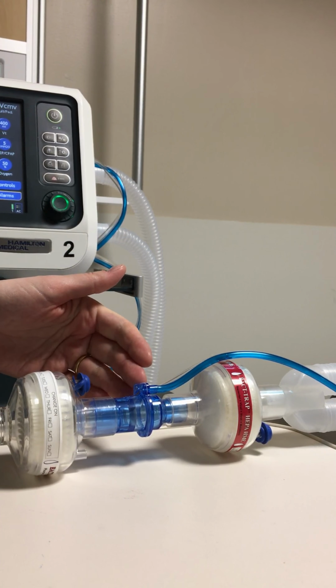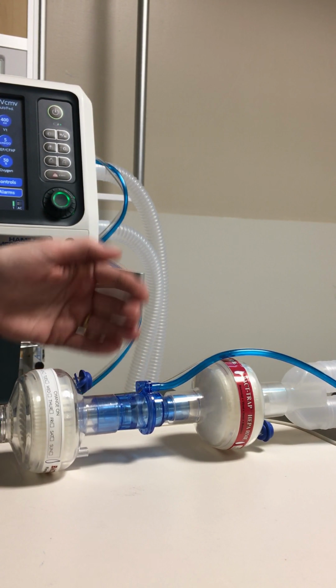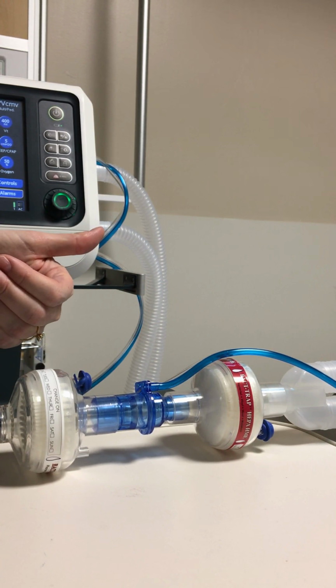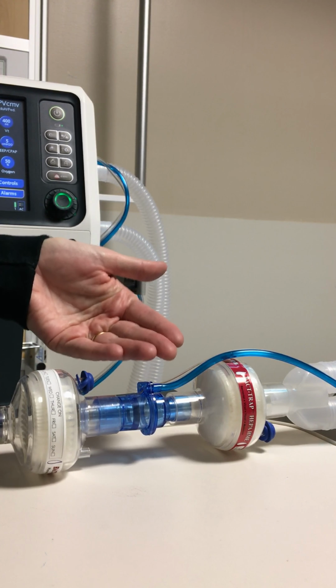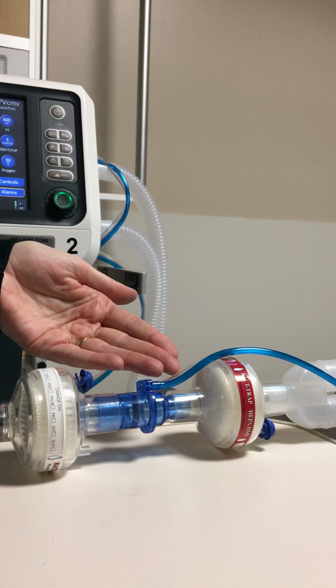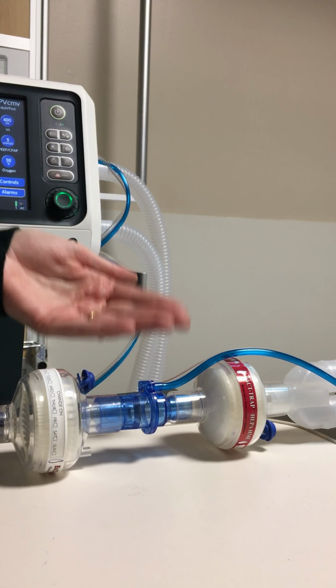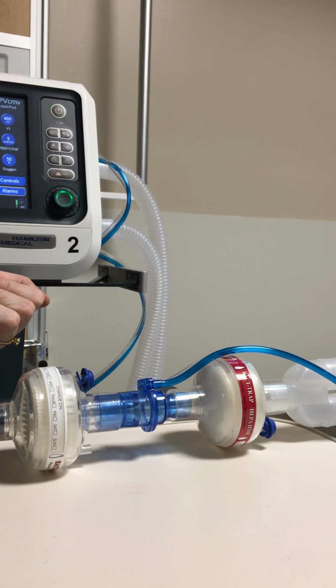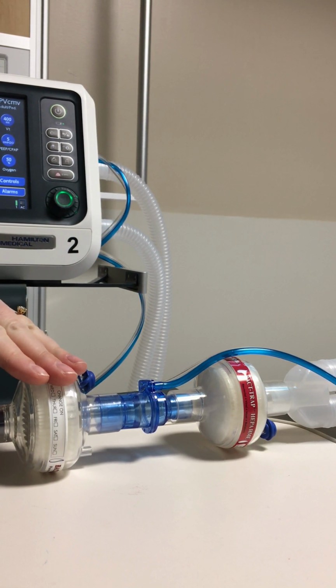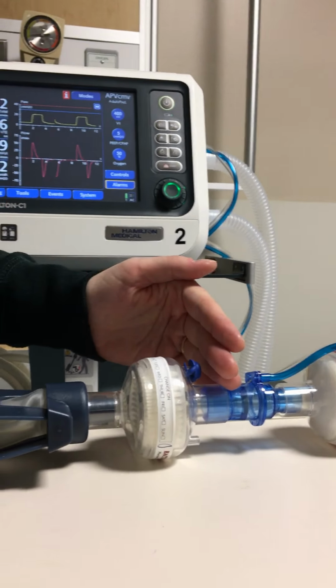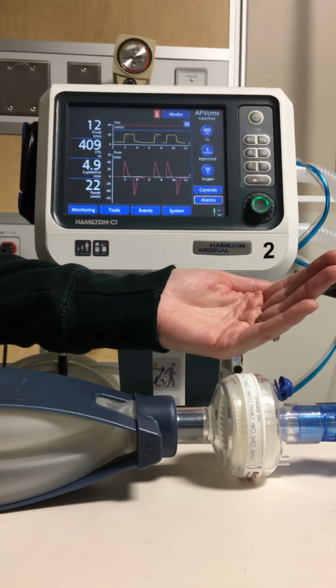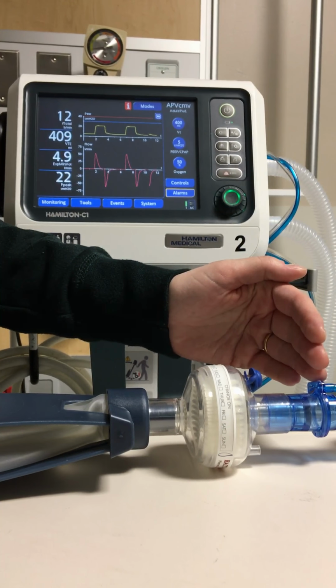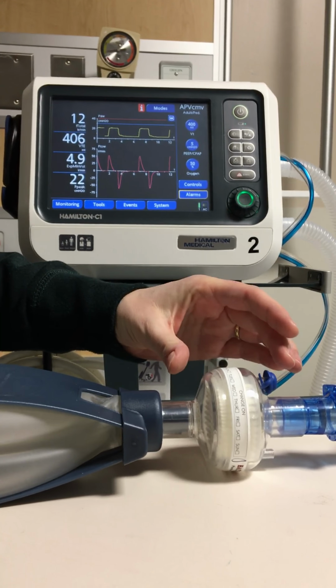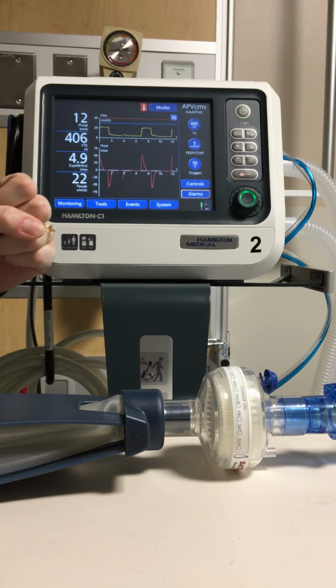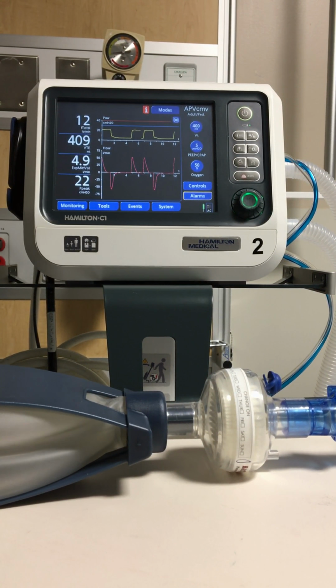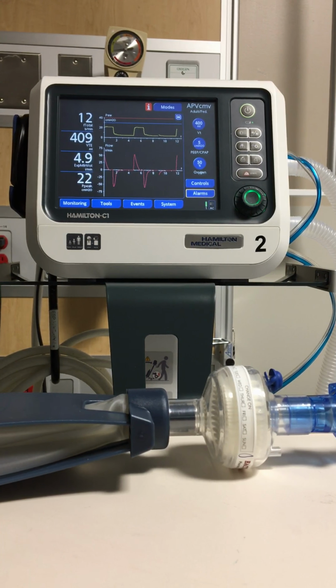The next piece is the flow sensor. We always want it pointing in this direction for our patient, and we always want the sensing lines pointing up so that they will not accumulate condensation, which would cause an error in the machine. This filter and test lung is representing our patient, so they would not normally be pieces in this equipment. Normally we would go flow sensor to the suction adapter or just to the patient elbow attached to their endotracheal tube or tracheostomy tube.